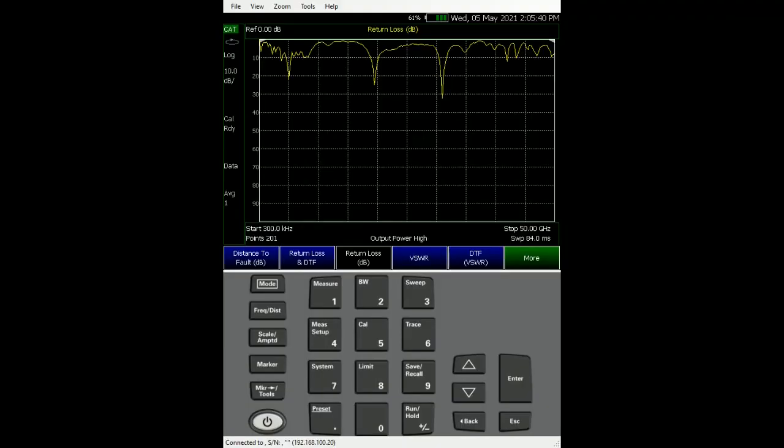In this video I'm going to show you how to set up the limit file in FieldFox. Sorry, not the limit file, limit line in the FieldFox to help you with the testing. In the events where you need to focus on looking at the board or the place where you do the measurements, you need some tools to notify you whether the readings on the measurements pass or fail, and this will be a very good feature to learn.